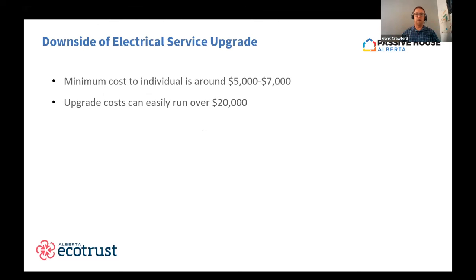So now back to some reasons you want to avoid that electrical service upgrade. First and foremost, there's some cost associated with it. Your lowest minimum cost to do an electrical service upgrade, going from generally a 100 amp service to a 200 amp service, is going to be in the $5,000 to $7,000 range. And this is only if the transformer that is feeding your house has spare capacity. The power line from the utility pole back to your building is either overhead, or if it's underground, it's in conduit. And the cable from the actual utility meter, generally on the outside of your house, to your main electrical panel can also be accessible. So if all those three things are there, then it might be the $5,000 to $7,000 range.